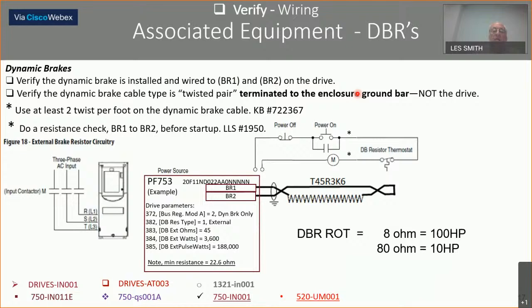And if you have a shield, don't attach it to the drive, attach it to the ground bus of the panel. And there's the knowledge base note for the dynamic brake cable, 722367. Just put a twist every foot to cancel out the noise that can come from that. And then do a resistance check. You can just easily, with the drive powered down, put that ohm meter across there and get a reading out there.